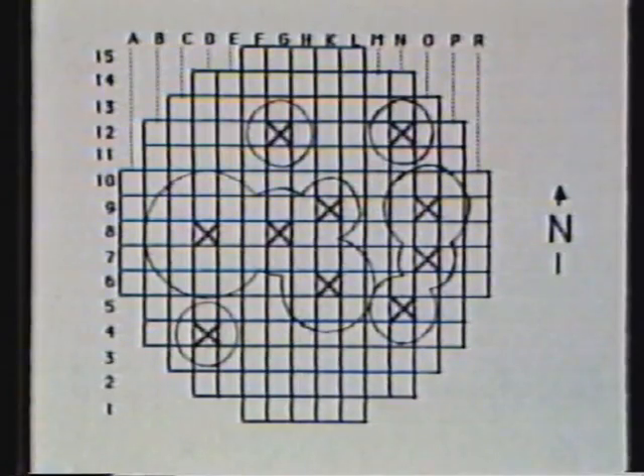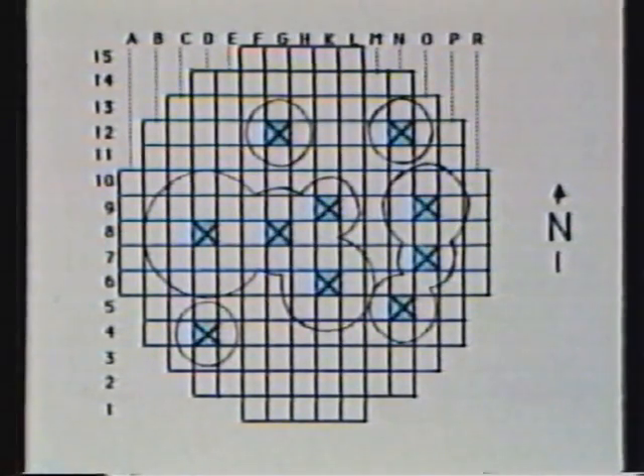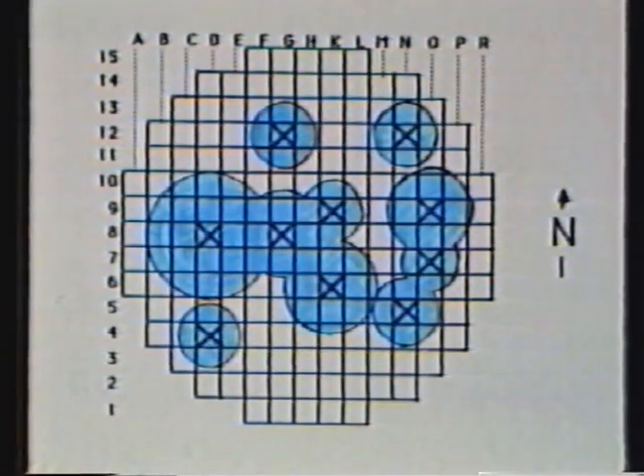Each box on this grid represents the location of a fuel bundle in the TMI-2 core. A total of 10 locations were drilled and surveyed. This allowed examination of a significant portion of the lower internals of the reactor vessel. These rods, which were below the waterline during the accident, appear bright and undamaged, except for some tearing caused by the drill.